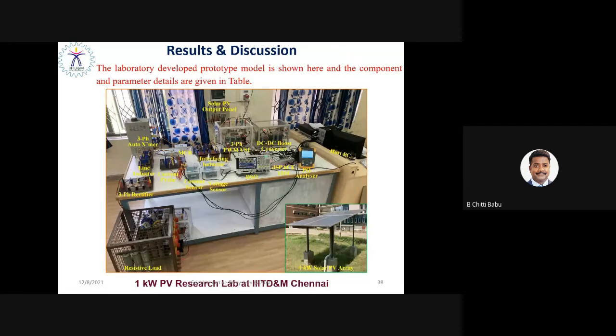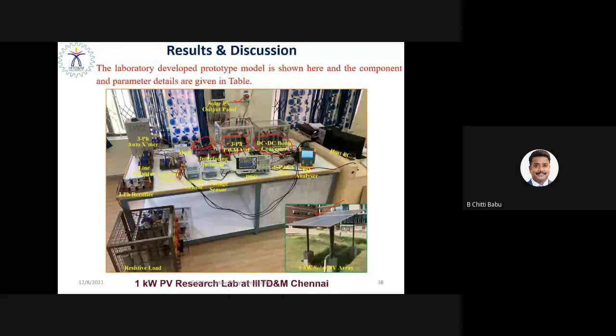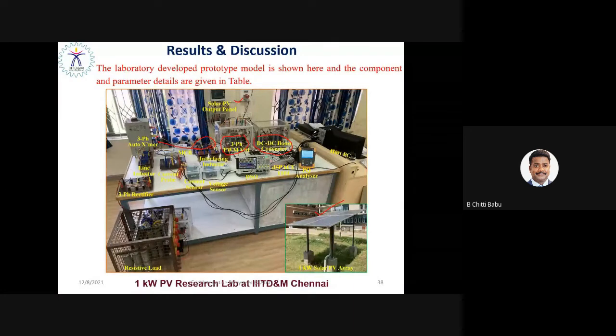Right. This is the laboratory prototype that we have developed in the PV research lab at IIITDM Kanchipuram, Chennai, having the PV panel installed outside of the building, and the outlets are available here with 1 kilowatt PV. The PV power is given to the DC to DC boost converter. Then the boost converter output is given to a 3-phase PWM VSI. The VSI output is given to a filter inductor, and then that output is given to the 3-phase autotransformer. This essentially acts as the point of common coupling, so that we can change the voltage level at the point of common coupling. Then the output is given to the line inductor. Then at the line inductor with the PCC, we connect a 3-phase diode bridge rectifier with a resistive load. So this is essentially a nonlinear load, right?